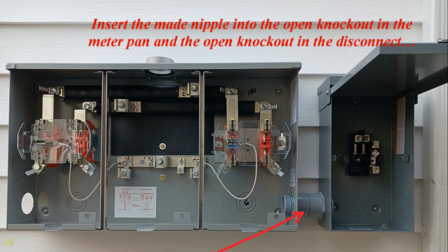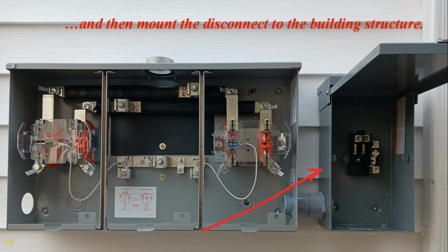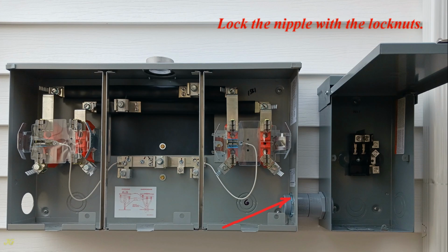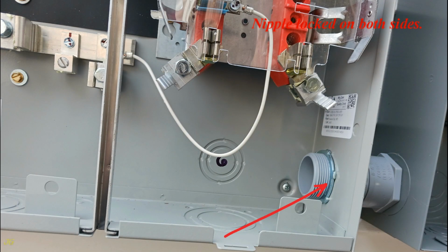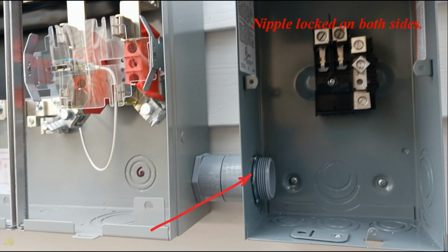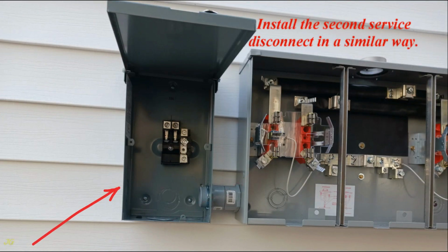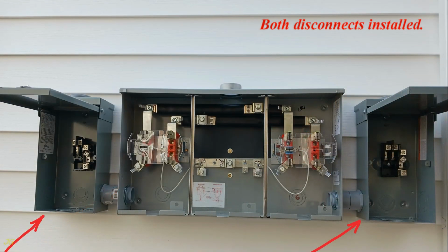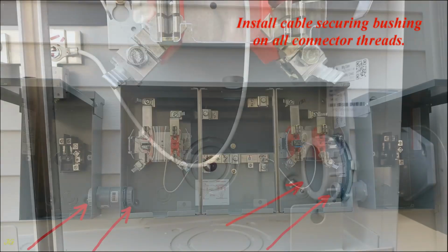Insert the made nipple into the open knockout in the meter pan and the open knockout in the disconnect, and then mount the disconnect to the building structure. Lock the nipple with the lock nuts. Nipple locked on both sides. Install the second service disconnect in a similar way. Both disconnects installed. Install cable securing bushing on all connector threads.